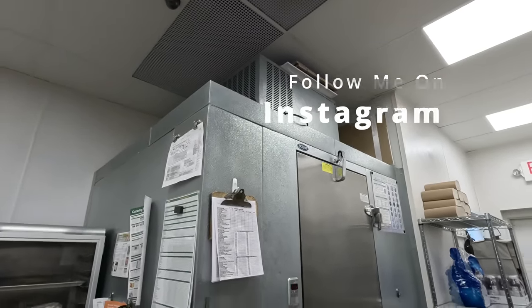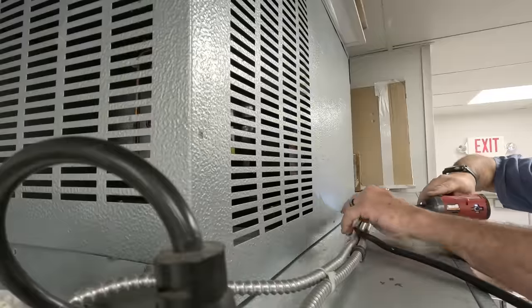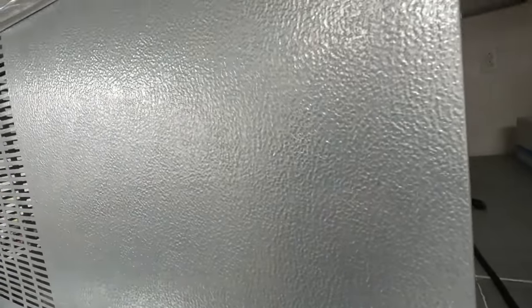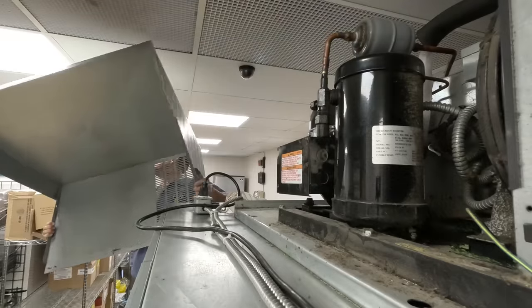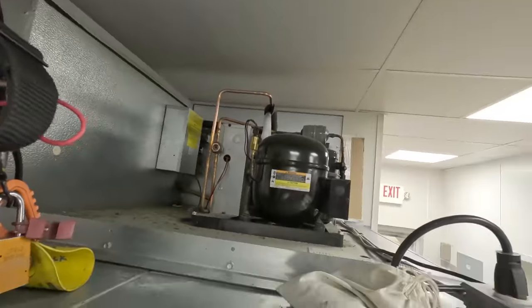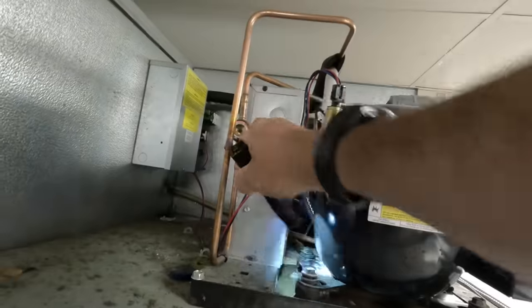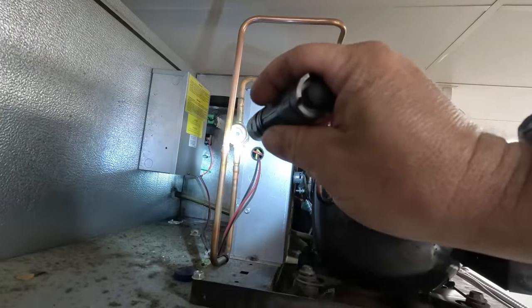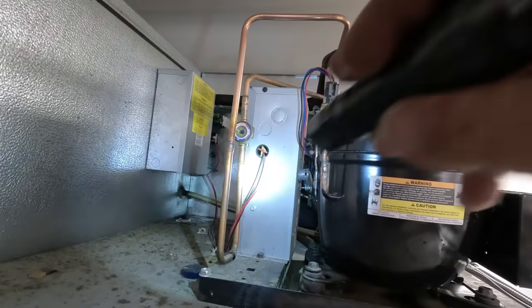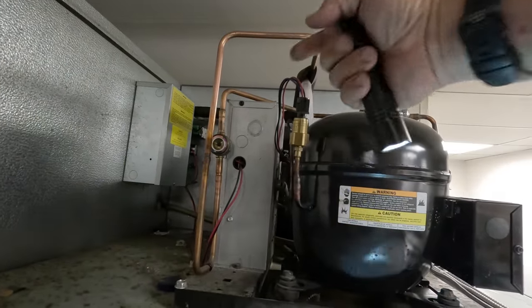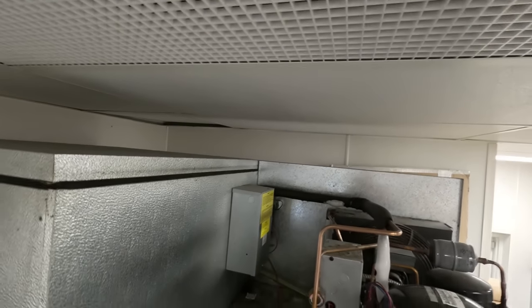Alright, so we're gonna have to get a ladder and see if we can get up there and get this thing melted out. So we found the controller and the condenser that's dirty. It says DF over there on that controller, so maybe it's got a failed defrost. Let's see if the sight glass is full. Appears to be. Looks like it's towards the dry mark. It's got that electronic stuff on there which could be failing.